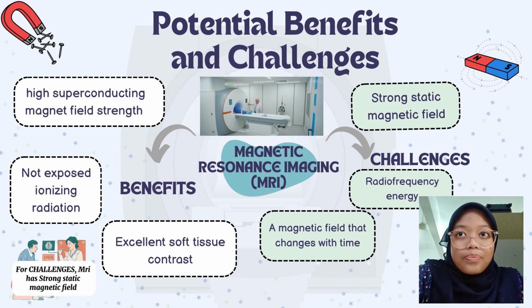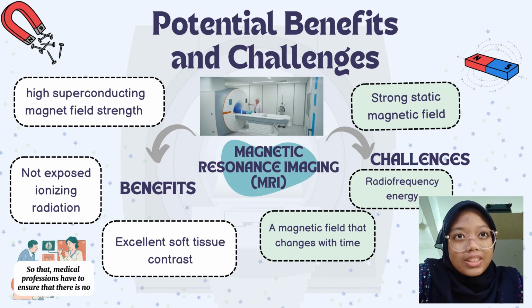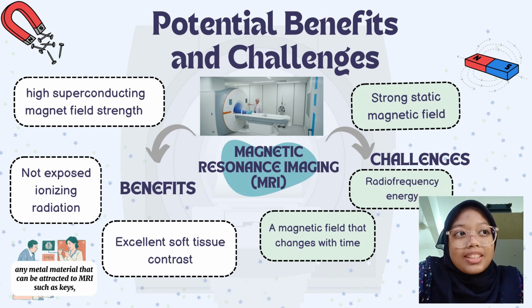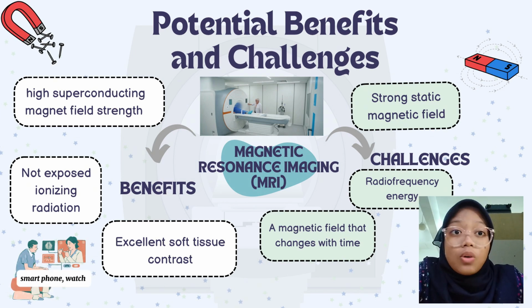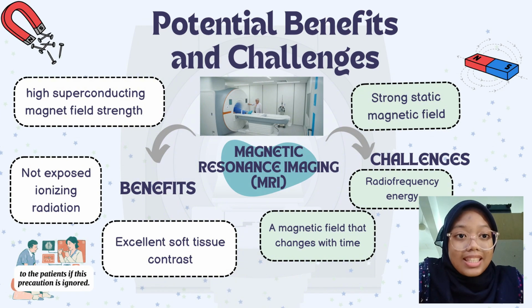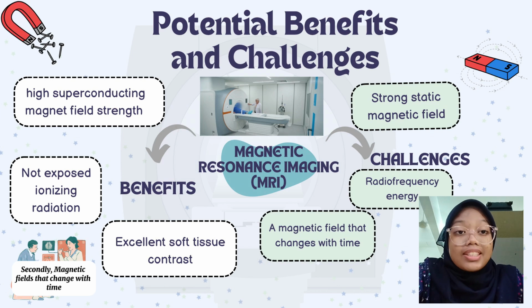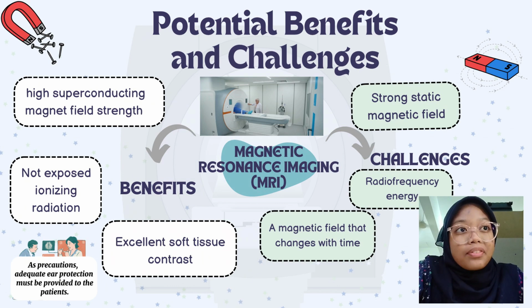For challenges, MRI has a strong static magnetic field, so medical professionals have to ensure that there is no metal material that can be attracted to the MRI, such as keys, smartphones, and watches. It will cause damage to the scanner or injury to patients if this precaution is ignored. Secondly, magnetic fields that change with time cause a loud knocking noise which may harm hearing, especially for patients. As a precaution, adequate ear protection must be provided to the patients.